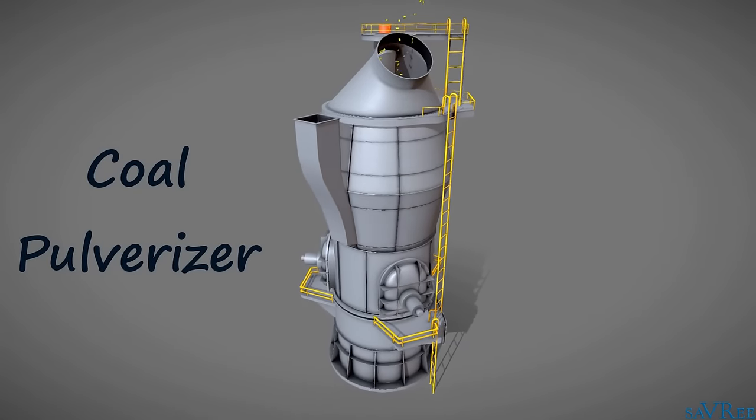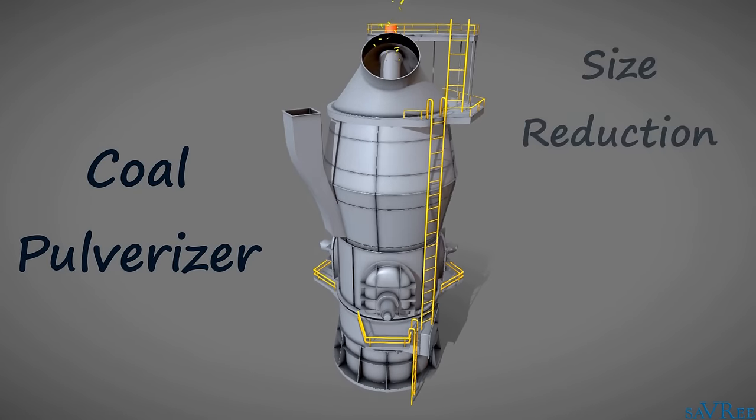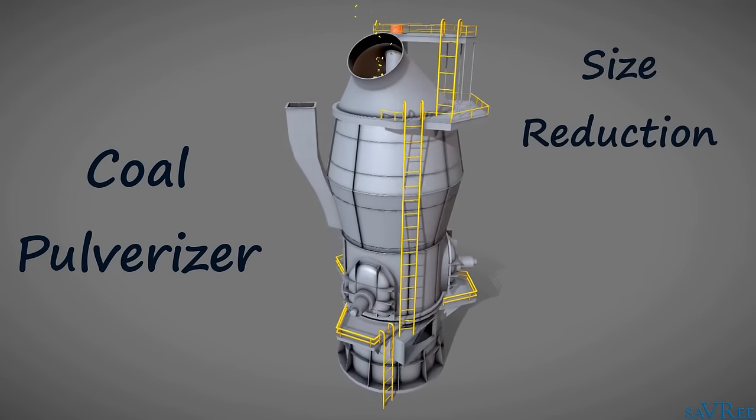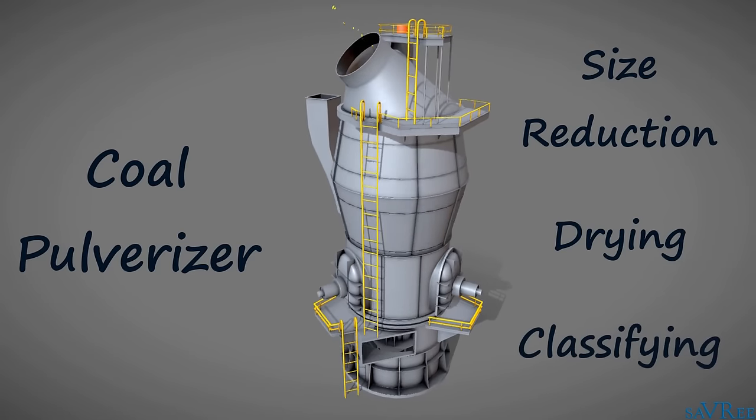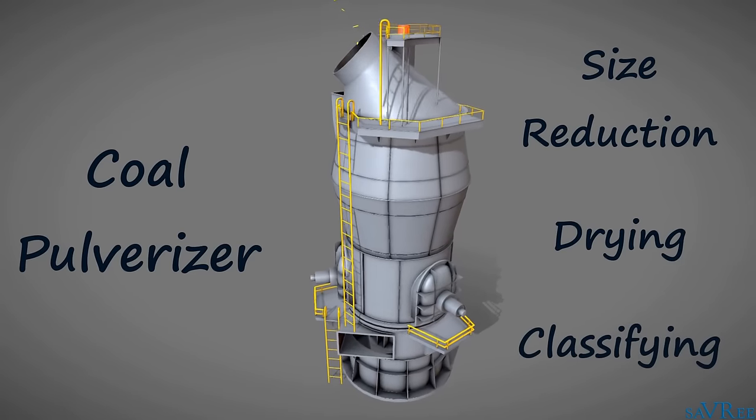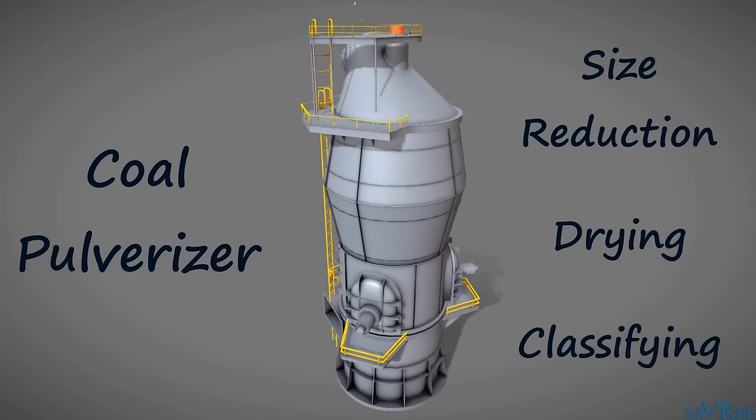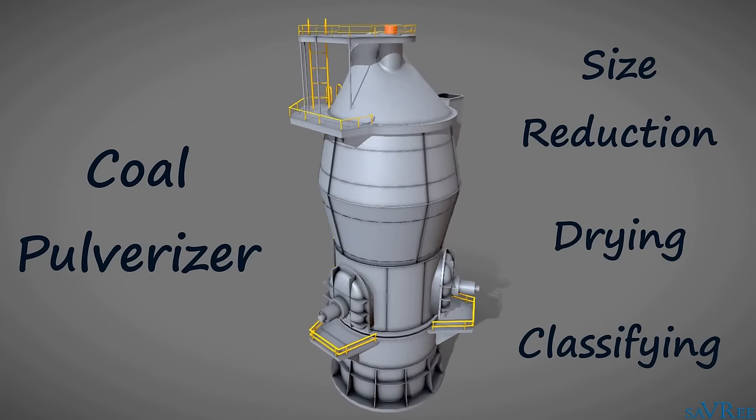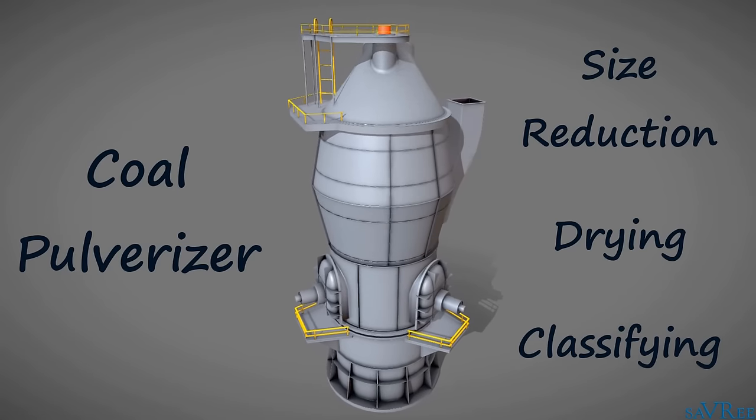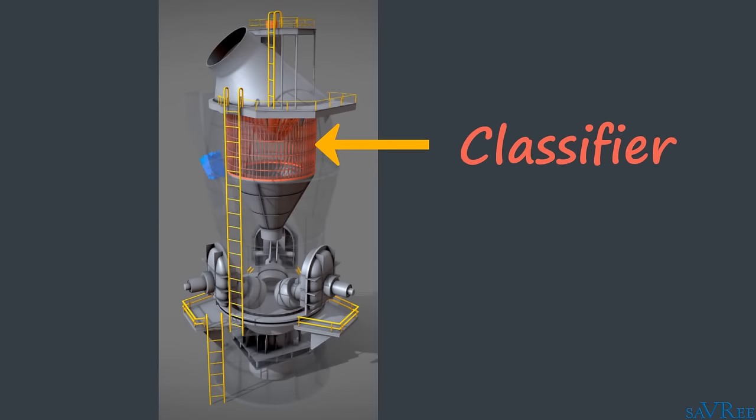When we pulverize coal, we're essentially reducing its size, drying it, and classifying it. Classifying means that we're sort of passing it through kind of a filter, you could say in a way, or a grate, and that ensures that the coal is the correct size when it gets to the boiler. We don't call it a filter or a grate, we call it a classifier, and usually it's a rotating object inside the coal pulverizer itself. If you want to learn more about coal pulverizers, then I will put the link in the video description area, because we've actually got a tutorial for that as well.